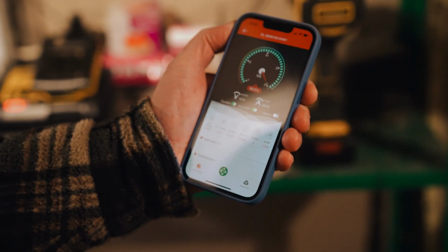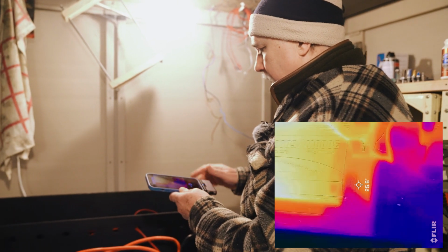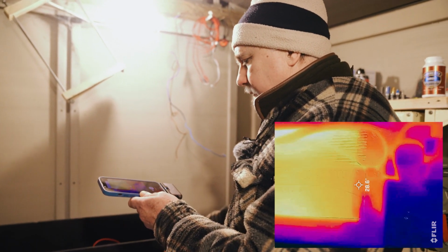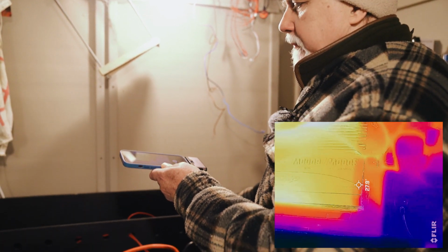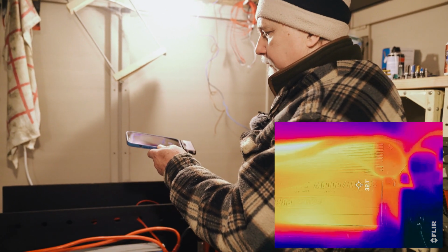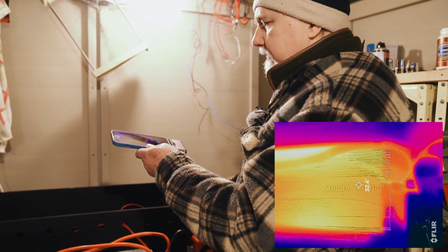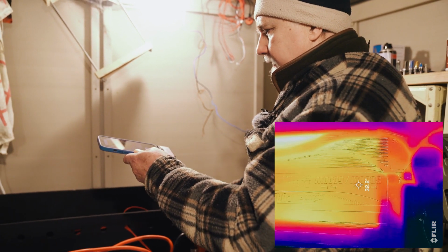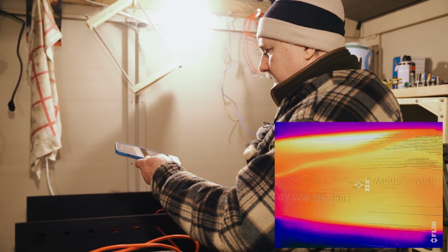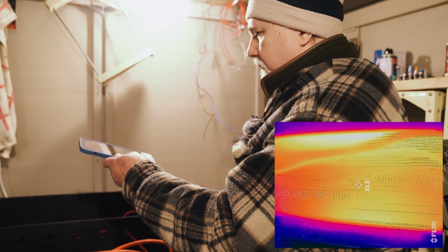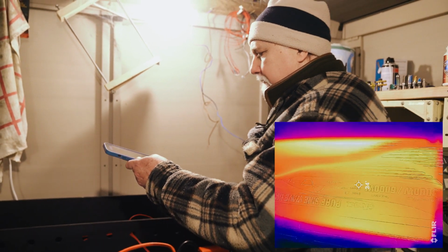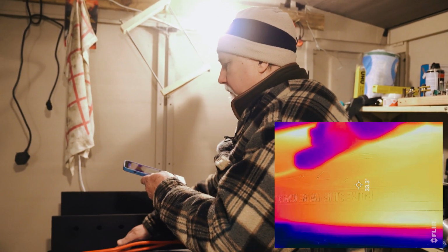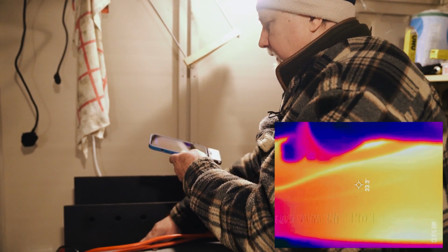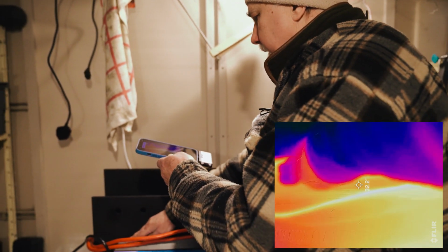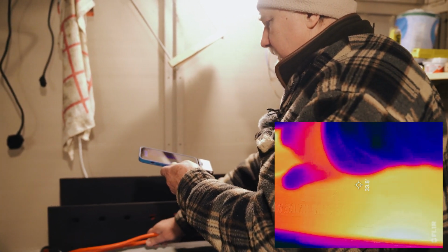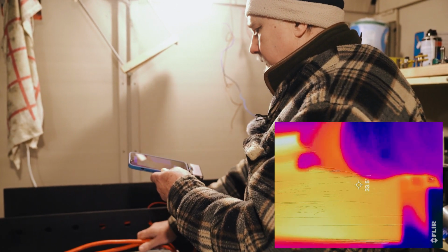With it running, that's drawing 270 amps, which is a good amount. We're monitoring this battery, well, the whole setup, the battery and the inverter, with a FLIR camera to see if there are any excessively hot areas. As you can see, the cooling fins on the inverter are probably the warmest, and they're absolutely fine. When I say they're warm, I'm touching them now by hand, and they're actually fine, just slightly warm. The cables are slightly warm too. Really nothing to worry about at all.